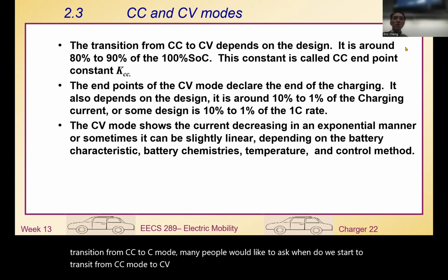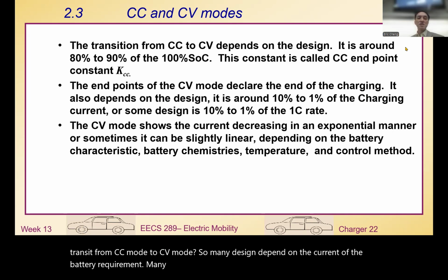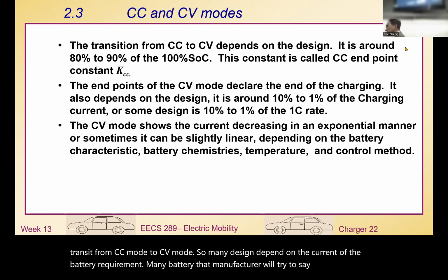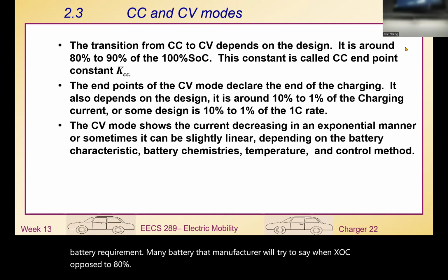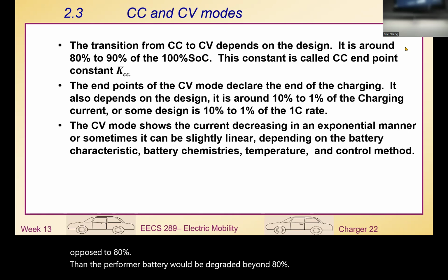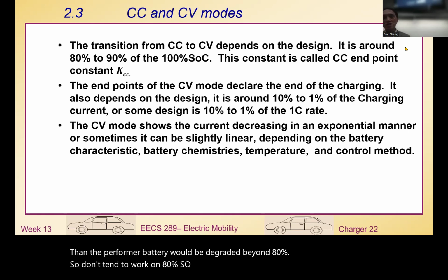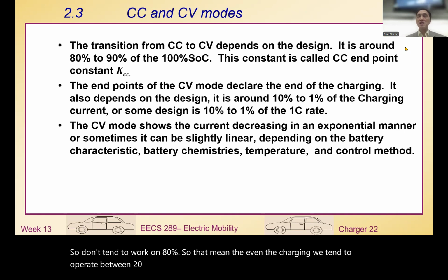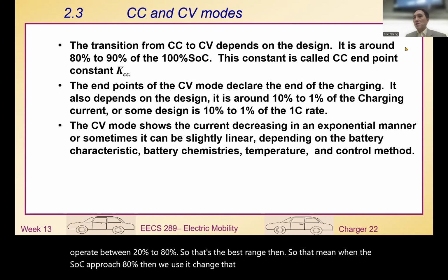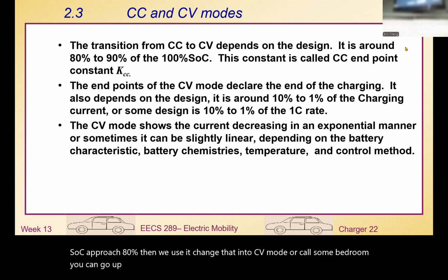Many designs depend on the current of the battery requirement. Many battery manufacturers will tend to say when the SOC approaches 80%, the performance of the battery will be degraded beyond that, so we don't tend to work beyond 80%. That means even for charging, we tend to operate between 20% to 80% - that's the best range. So when the SOC approaches 80%, we usually change into CV mode. Of course, some batteries you can go up to 85% or 90% before changing to CV mode, but 80%, 85% are just common numbers we use.